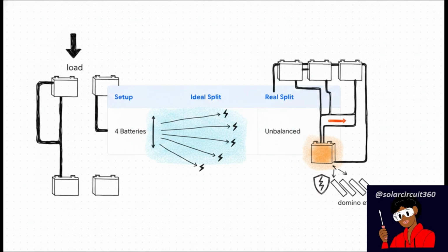In reality, electricity is incredibly lazy. It will always take the path of least resistance. So slight differences in cable lengths or how tightly a bolt is screwed down create different levels of electrical resistance. This forces one single battery in your bank to take on way more of the load than the others. It works harder, it heats up, and eventually it triggers its own BMS shutdown, which then creates a catastrophic domino effect across your whole system.